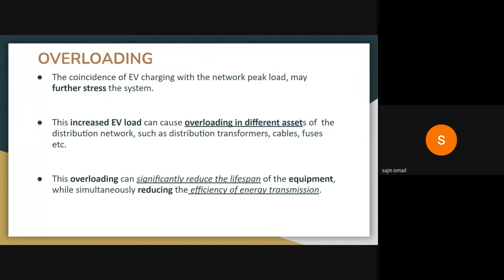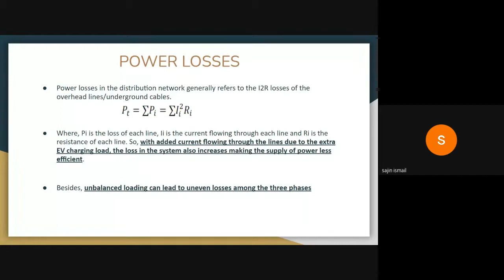Now the power losses - as demand gets high, current will be high, and I square R losses will be high, so power losses will be there. With this added current flow through the lines due to extra EV charging load, the loss in the system increases, making the supply of power less efficient. This unwanted demand comes when the network is not ready for it, so losses will be high. Also, unbalanced loading can lead to uneven losses among the three phases we discussed earlier.